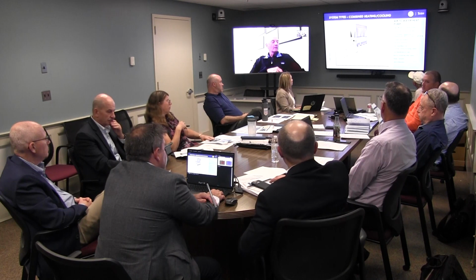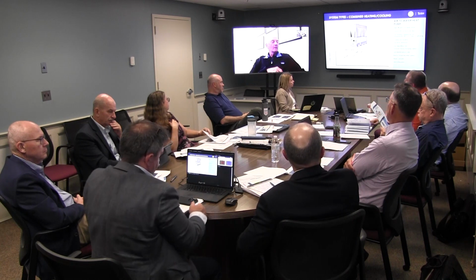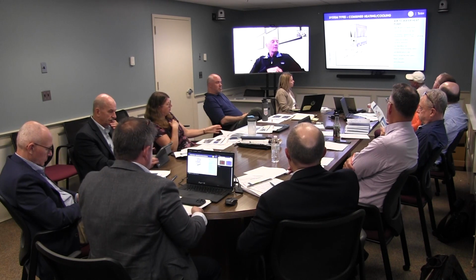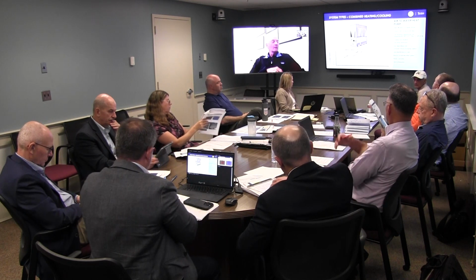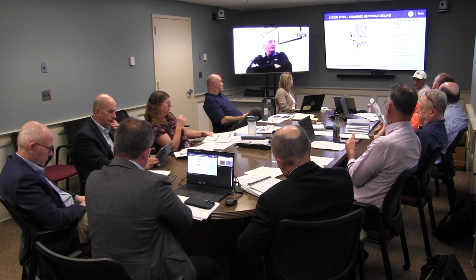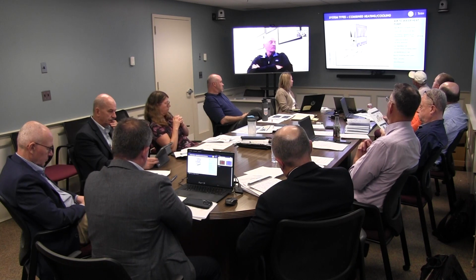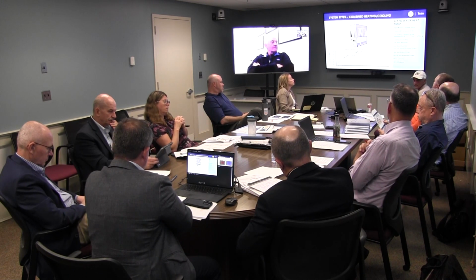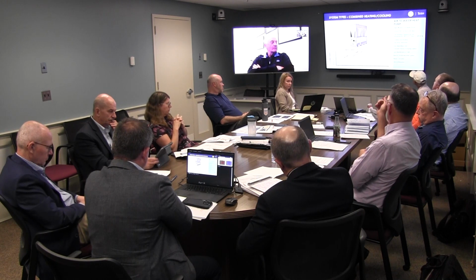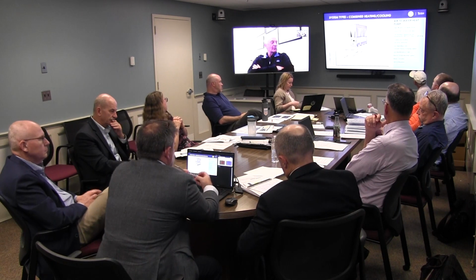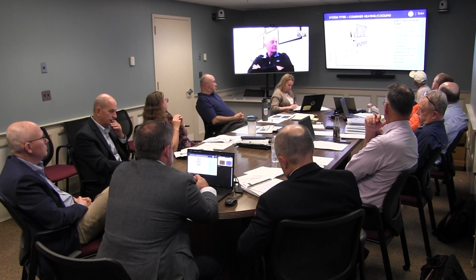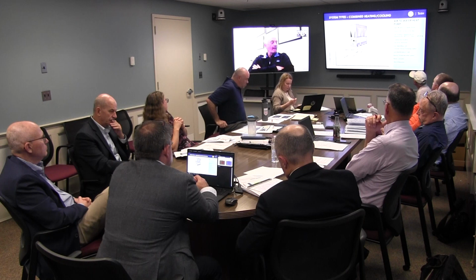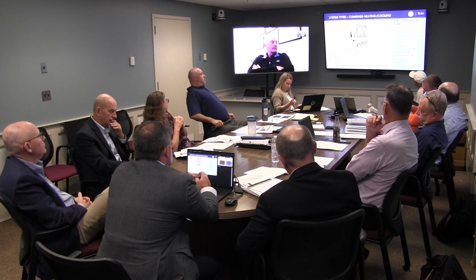I didn't present this for the school. This is an air-to-water heat pump, which is coming really hot to the market now for decarbonization. What this does is take ambient air and use that air to create either hot water or cool water with compressors to deliver heating or cooling to the building. The problem with these things in our climate is they're not very efficient when it gets cold outside. So this particular one is 100% capacity down to 17 degrees, but as you go down, it's only 30% at -20, it's 65 actually, but the temperature of the water is only 86 degrees.